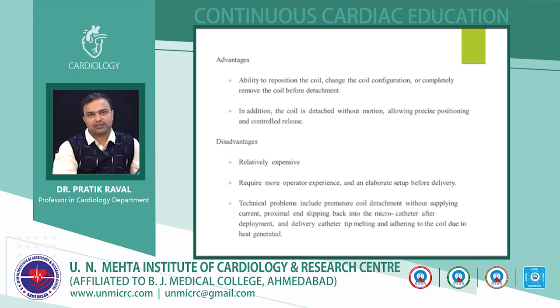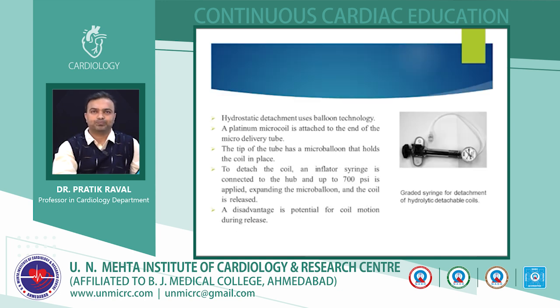The main disadvantage is that these coils are relatively expensive, they require expertise, and an elaborate setup is required while delivering. The technical problems that can be encountered with this electrolytic mechanism are that the coil can get prematurely detached even without supplying the current. The proximal end of the coil can slip back inside the microcatheter, and then we encounter difficulty delivering the coil into the vessel. The delivery catheter can also melt because of the heat generated by the current.